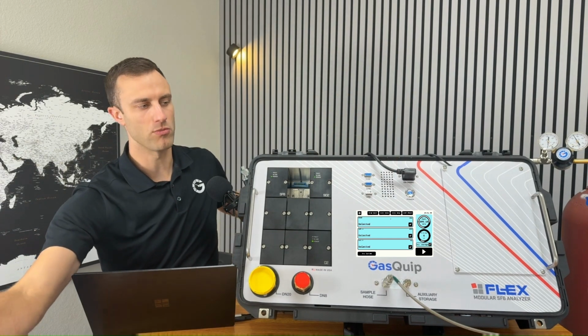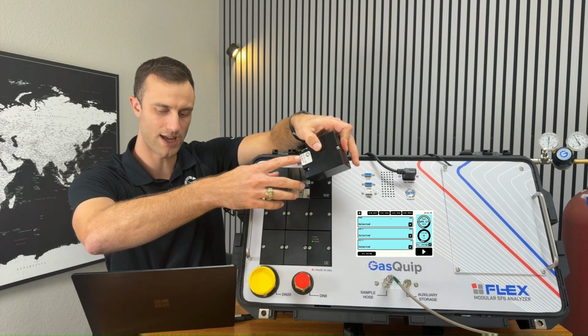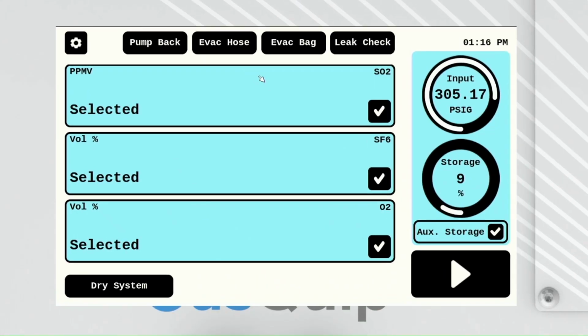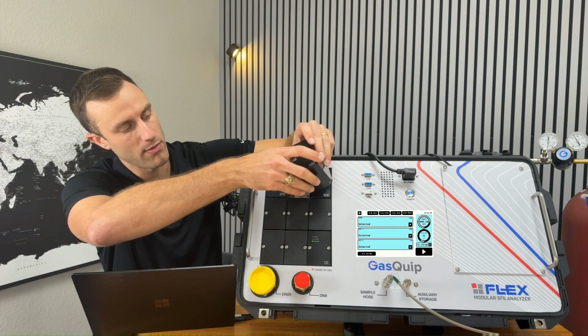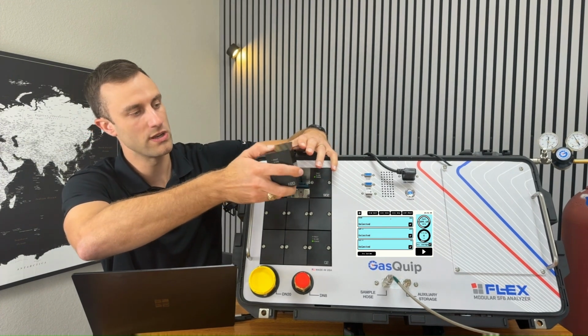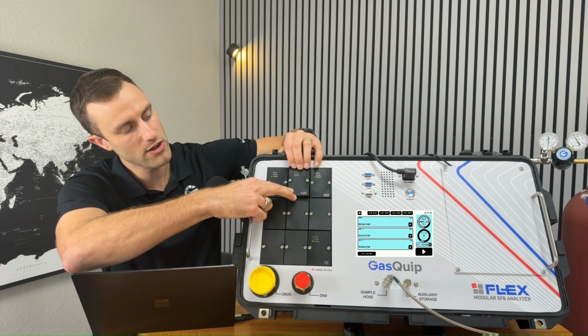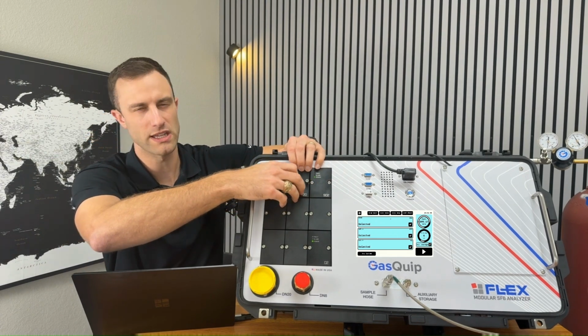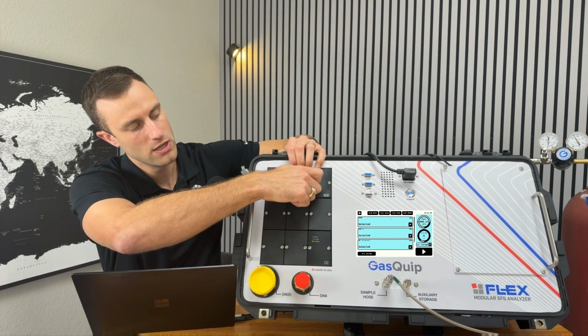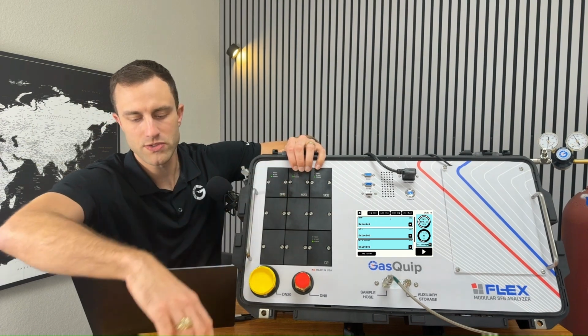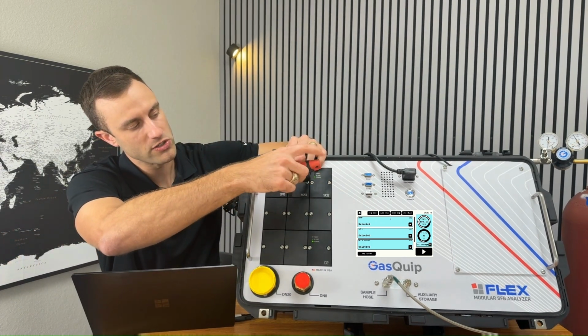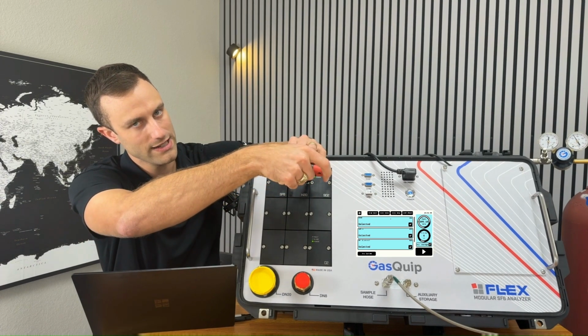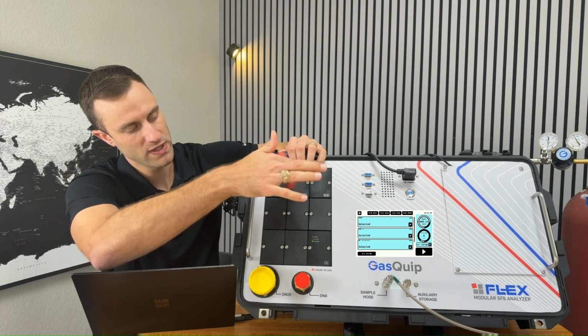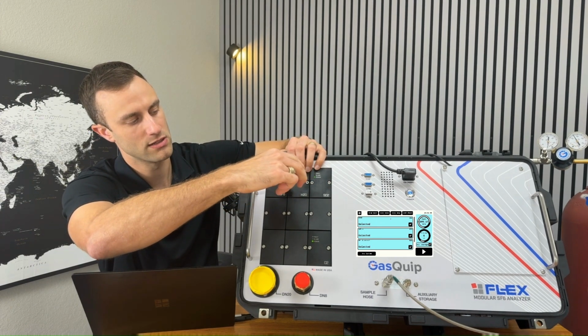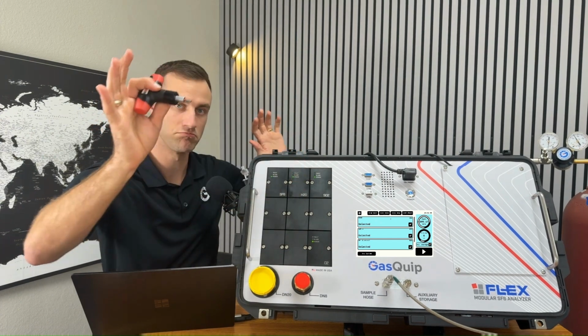So we'll grab our other module, our new replacement module, serial number on the side here to let you know. And if we take a look at our analyzer, it'll show that we no longer have a H2O module plugged in, and it'll pop up automatically once we install the new one. So to install the new one, we have just to push this down, and once you get it in position, you push it down and it'll click in, almost like an old Atari cartridge. And you're gonna tighten down both bolts. We're gonna use our preset torque wrench, and we're gonna screw either side down until we hear a click. That lets us know we're at the right torque setting and compresses the bottom O-rings at the right amount. And you get a click whenever that's done, and you're good to go.